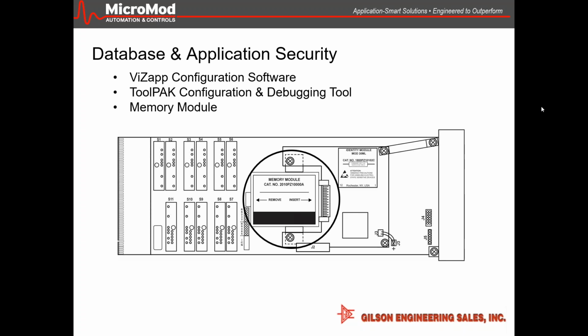So we got to read them out loud since not everyone else can see them. The first one: can I give you my 352 or 353 controller with the iWare software, and can you program it as well, so all I have to do is mount and wire it? Absolutely, that's standard configuration. We don't mind getting it on paper, but if we get it with iWare or iConfig, we have all the spans, ranges, trip points, all the information that may or may not be on a paper-based copy.